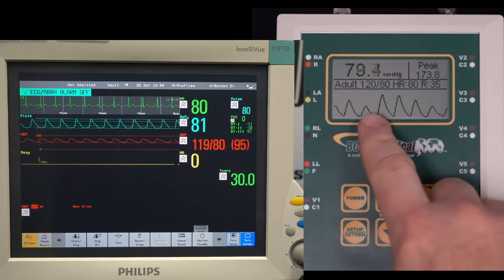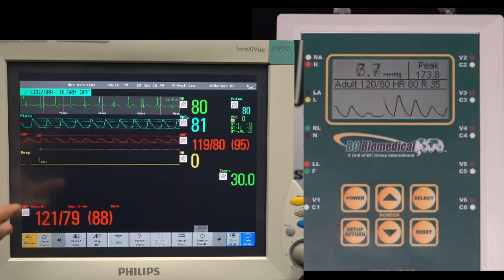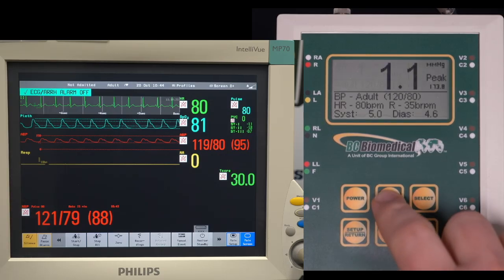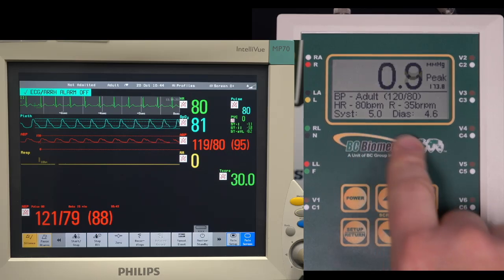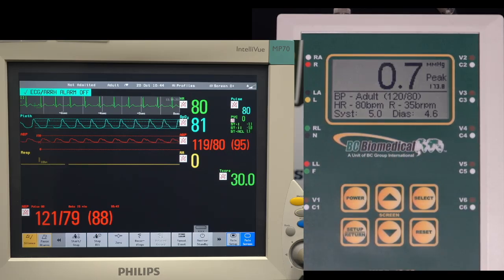Now I have it set for 120 over 80, so I would expect my monitor to get 120 over 80. Now what happens is we have an algorithm inside our unit that says, when the pressure reaches this point, produce a pulse of such amplitude. Now the monitor is also going to be looking at those pressure pulses that are coming back. They all have their own algorithm. So Philips is going to be different than Mindray, is going to be different than Welch Allyn.